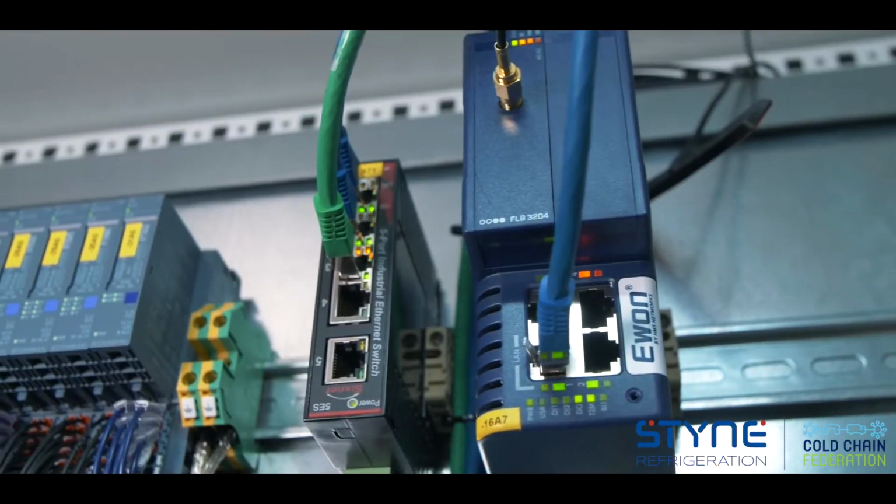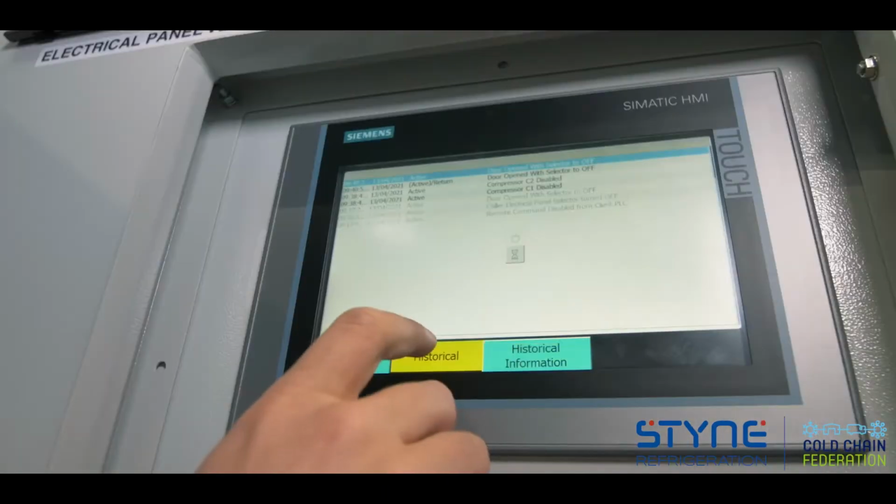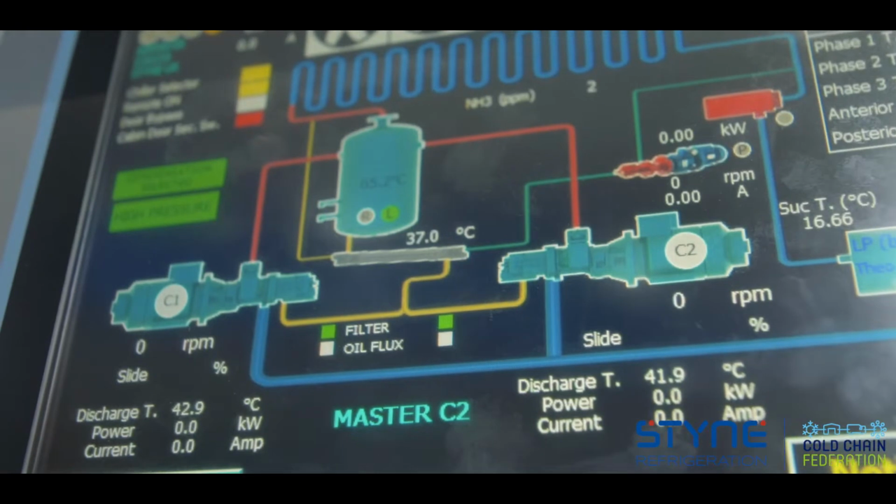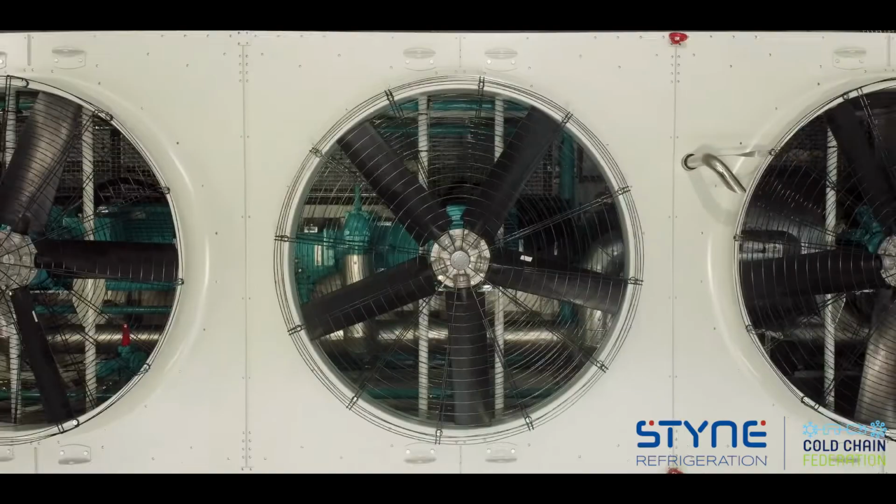Where our product is, should we say, niche, suitable, call it what you will, it uses ammonia, which, as everybody who uses ammonia in a refrigeration system will know, is good down to around about the mid minus 30s, something like that. So with the judicious application of a heat source onto an absorption chiller, we can facilitate an existing store or a new store that wants to run a low temperature application, say minus 25, minus 30, with very, very little power consumption. And when I say little, I mean around about 90% less than you're currently using.